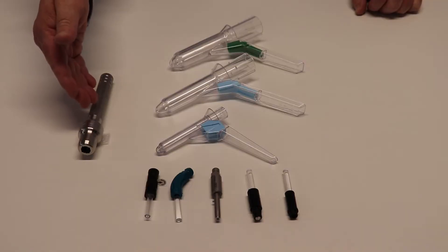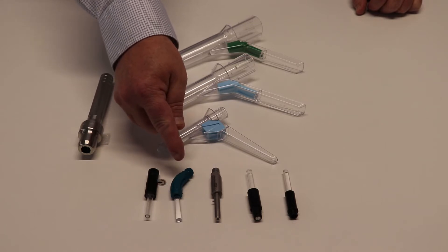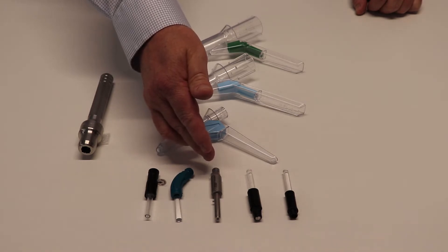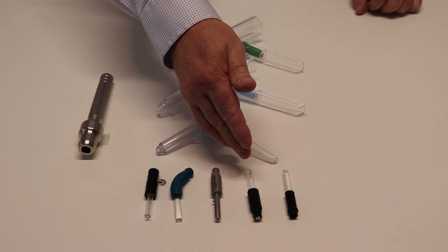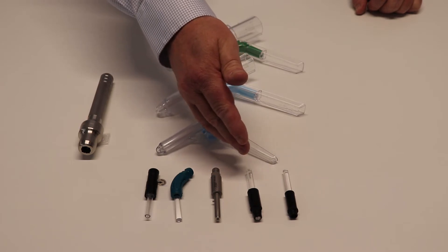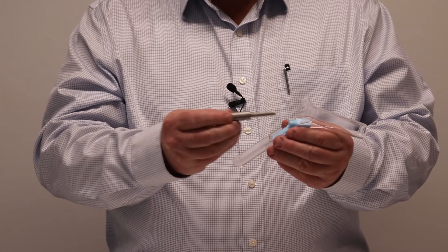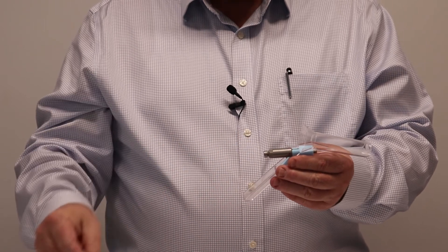This light source works in conjunction with a curved disposable connector. We can also supply reusable stainless steel connectors, and there are other options for connecting to Welch Allyn or Olympus type fibre optic cables and equipment as well.